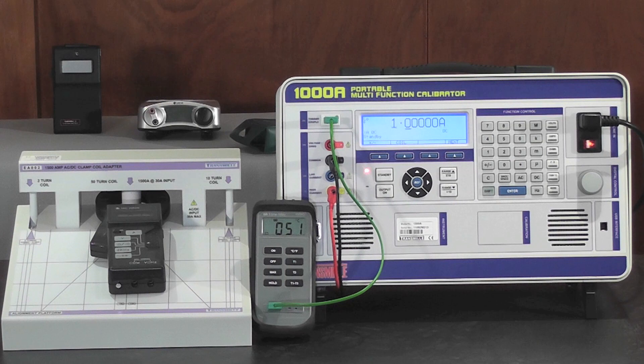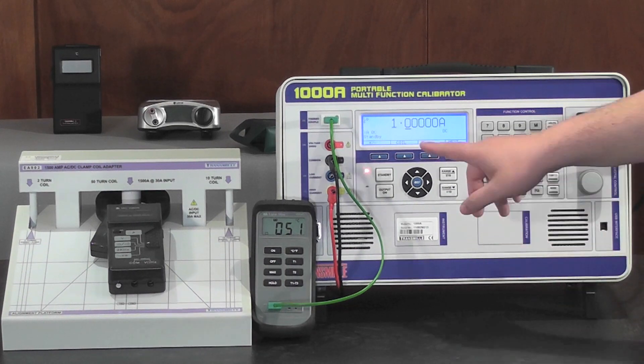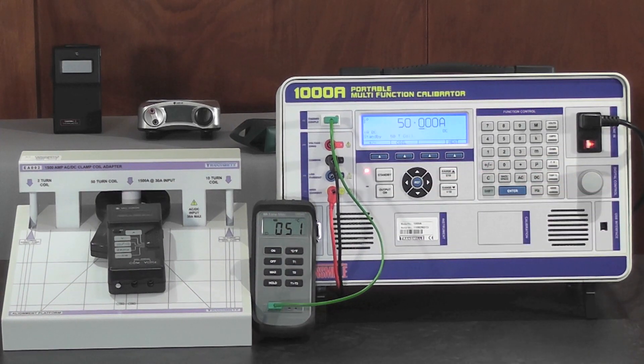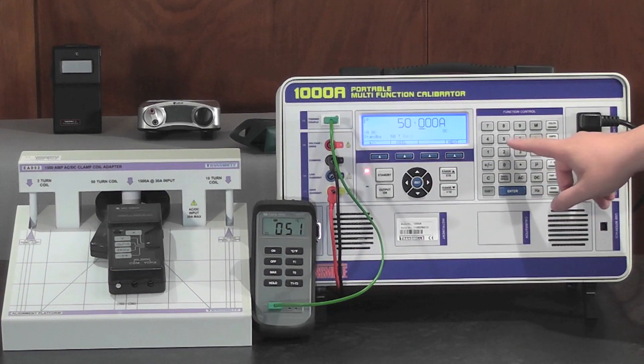For the calibration of clamp meters, use the soft key to select the coil. Then select the number of turns. Then with direct current entry, enter in the desired value, for example 50A.